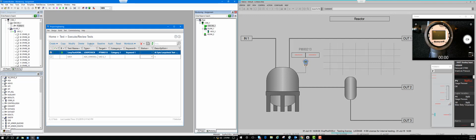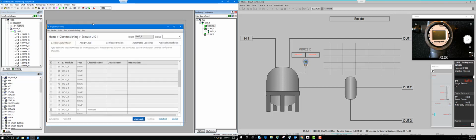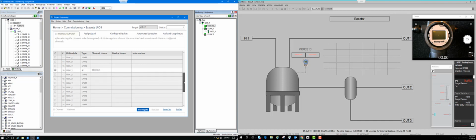I'm going to go ahead and execute my loop test here. So automatically what it does, it interrogates the card. It's a 32 channel UIO2 version 2 card, Universal I/O version 2. And it did find my PT800. This is what I'm expecting: my channel name is PT800 on channel 16. So if I go interrogate, Experion is going to go into the UIO2 module and search for the instruments attached to the channels. Okay, so it turns it on, as you can see here to the right. It did turn the instrument on long enough to interrogate its HART properties. Okay, so there we go, it's on.